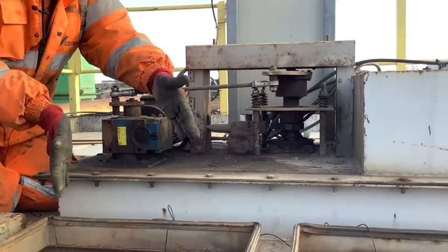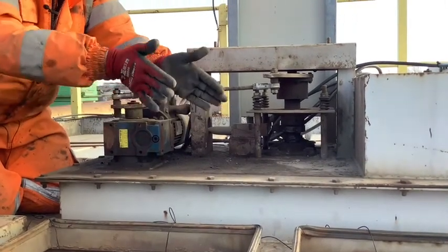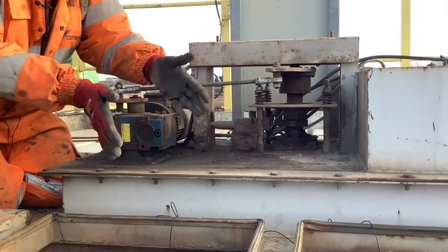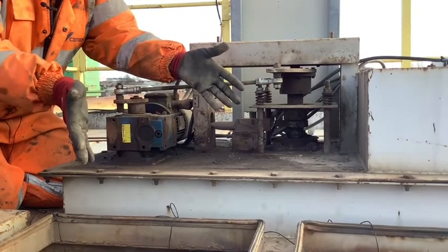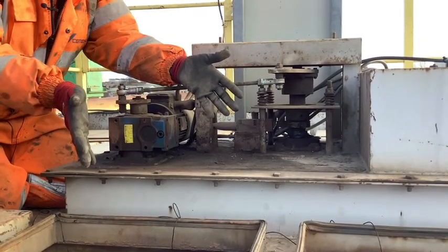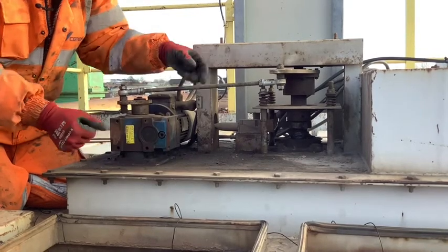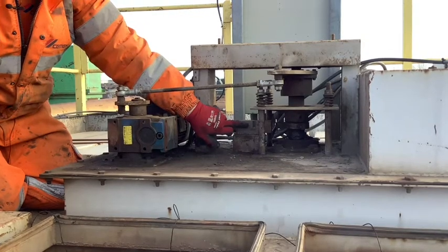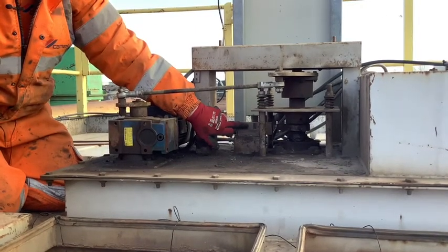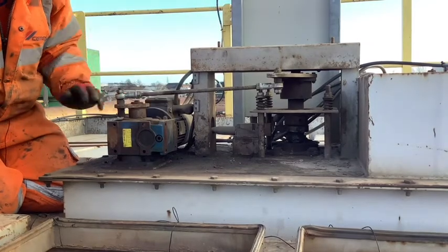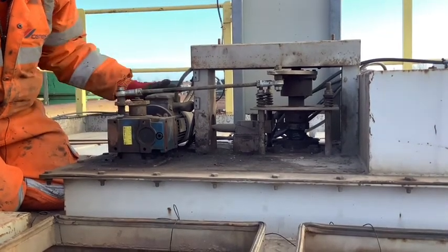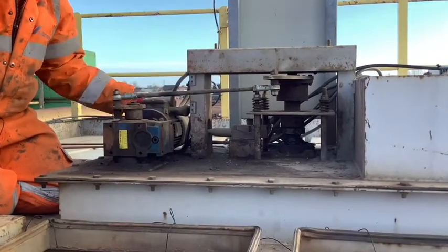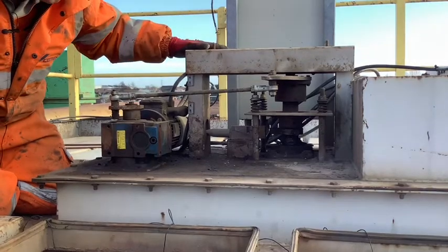Very important that this is aligned, because if not, the free clean mechanism will attempt to go in between cells and not clean your bags fully. So this bar is crucial to the maintenance of the system to ensure that everything is cleaned. So give your rod a check. We've also got a proximity or a limit switch which makes sure that the cleaning mechanism is in the position it should be. We've got a motor and gearbox. We're looking for oil leakage, we're looking for wear, anything else on the system that can affect its performance. So good luck round that to start off with.